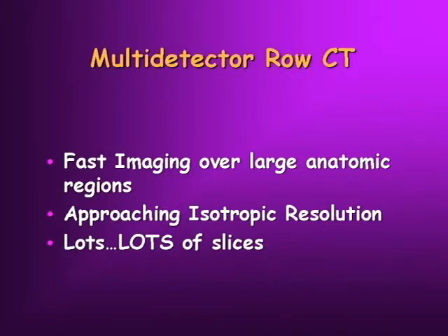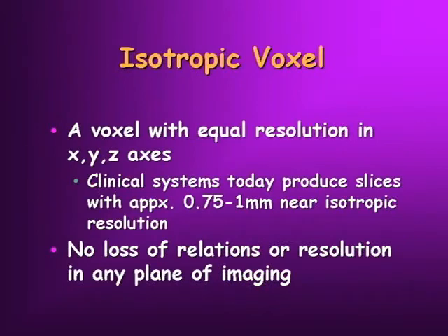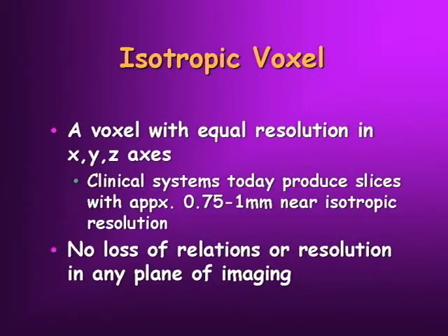And how do you deal with those? So first, the isotropic voxel — that's a voxel with equal resolution in the X, Y, and Z axis. Today's clinical systems produce slices that are near isotropic voxel resolution, a little bit of broadening in the Z axis, but for the most part they're very close. And what that allows you is no loss of the relationships or resolution in any conceivable plane of imaging to acquire that volume of data.